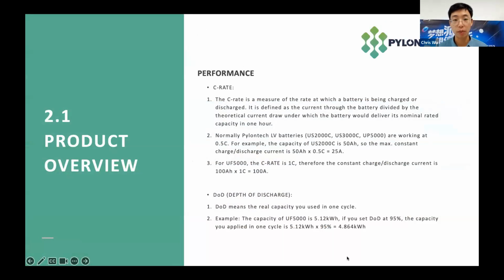Before talking about the specs, I will go through two performance parameters. The first one is C rate. The C rate is a measure of the rate at which the battery is being charged or discharged. It's defined as the current through the battery divided by the theoretical current under which the battery would deliver its nominal capacity in 1 hour. Our low voltage batteries, 2000C, 3000C, and UP 5000, work at 0.5C, which means they can charge or discharge fully in 2 hours.